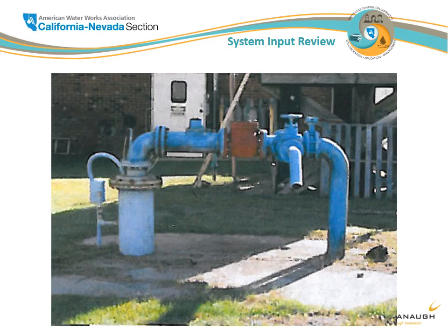So the relative positioning to the valve right next to it, and to the 90-degree bend upstream and downstream, is a really big deal. This is a meter that is not in a place where the flow is conditioned and smooth, and meters generally need smooth, conditioned flow to perform properly.